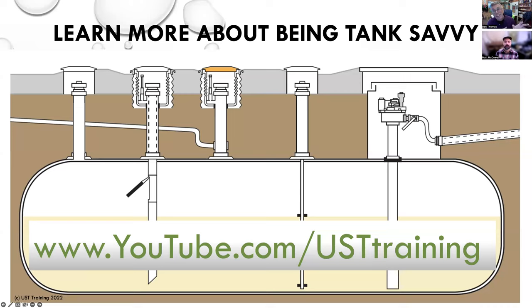One thing I didn't tie into this: if you're doing a static leak detection test, the tank has to be at least 50% full. With CSLD, you don't need to worry about tank volume, but if you only have periodic testing, you always have to be managing your fuel level so there's enough fuel in the tank to get a passing test.